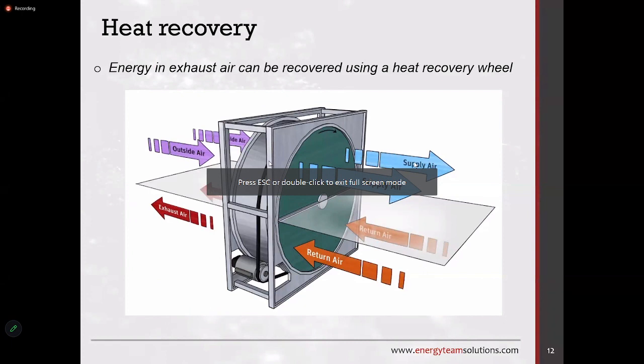Okay. So this is now an exhaust heat recovery system, which is mostly used in India, but I don't know, in Sri Lanka we do not practice this type of heat recovery system, where you recover from the exhaust air. Even if you're exhausting from a toilet or a kitchen, the space could be an air conditioned space. Then you're pulling out air which is conditioned, at a lower temperature, and just taking it outside, which is a heavy energy loss, just like the blow down of a boiler system, which we discussed. From a boiler, you blow down the high density water. So here you're removing an odor or a bad particle like carbon monoxide or CO2 from a conditioned space.